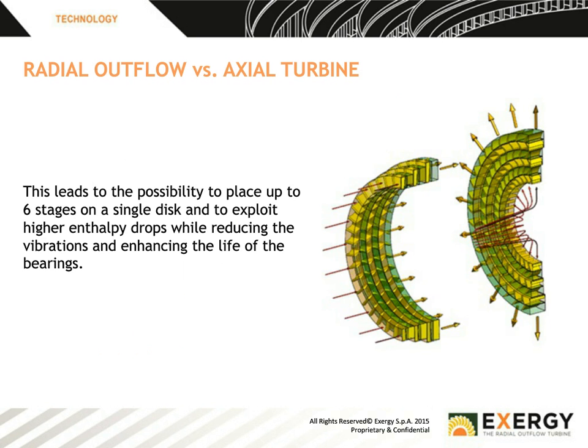I said up to 6 or 7 stages on a single disc allows us to exploit higher enthalpy drops. So this is particularly important on heat recovery applications that we're discussing today. Basically, if you do a heat recovery application, you have a large enthalpy drop, and you want to design each stage of the turbine to suit the enthalpy point where it is operating. If you can do 6 or 7 stages compared with a maximum of 2 or 3 stages, you have that opportunity to design each stage for each specific enthalpy zone. And we end up with significantly higher efficiencies.